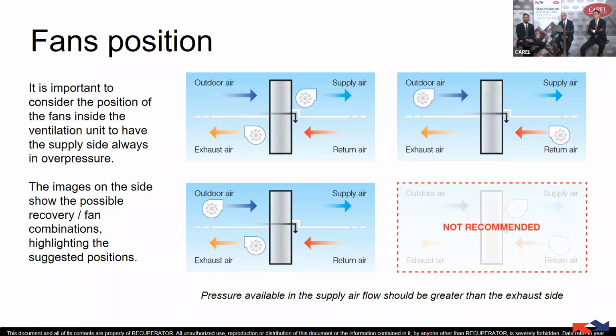We have here 3 out of 4 configurations that are good, where, as we've seen before with the pressure difference, we can direct the leakage from the supply to the exhaust. In that way, we can avoid any type of cross-contamination. It's important to understand the difference between leakage and contamination. With a correct fan position, we can direct the leakage, avoiding any type of cross-contamination.